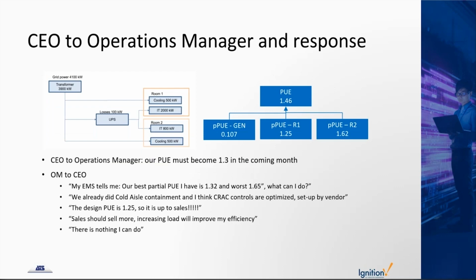So the next step is the CEO went to the operation manager. He said, well, I had a visit from the local administration. Our PUE is too high and it should become below 1.3 in the coming months. So the operation manager responded to the CEO, well, that's very nice, but if I look at my EMS, the best part of my PUE is 1.3, my worst part is 1.6. And what I already did, I did cold aisle containment. The vendor of the CRACs and the air handling units and the chiller came by, they optimized their equipment. So I think I did everything I could.